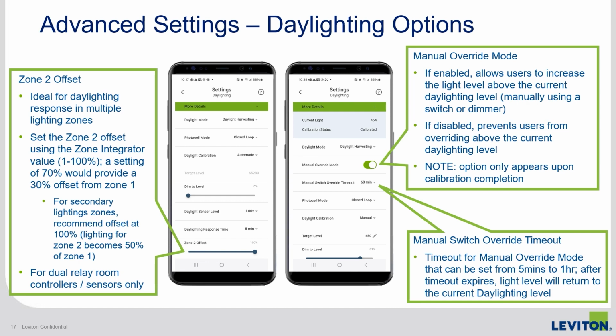In this mode, a person in the room or space can manually increase the lighting above the target levels. If that mode is enabled, there's also a timeout associated with options of 5 minutes to 1 hour. After that timeout expires, the lighting level returns to the current daylighting level.